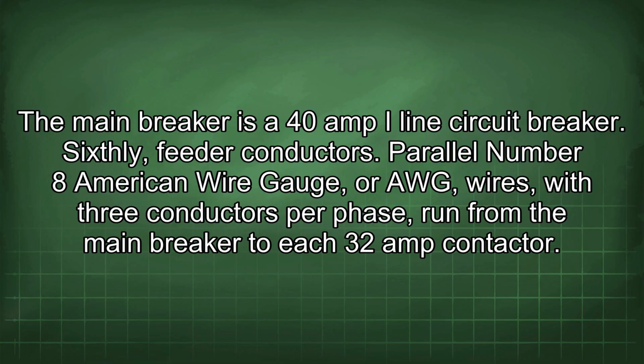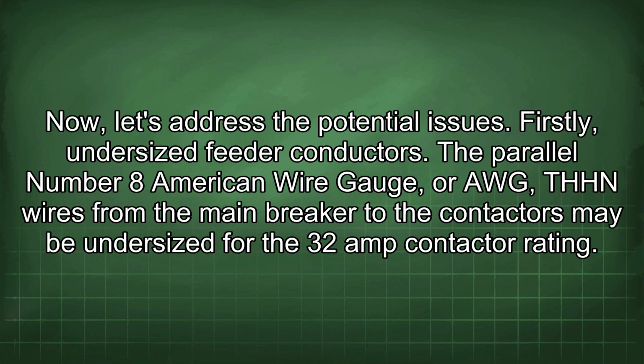Sixthly, feeder conductors. Parallel number 8 American wire gauge, or AWG, wires, with 3 conductors per phase, run from the main breaker to each 32 amp contactor. Now, let's address the potential issues. Firstly, undersized feeder conductors. The parallel number 8 AWG THHN wires from the main breaker to the contactors may be undersized for the 32 amp contactor rating.